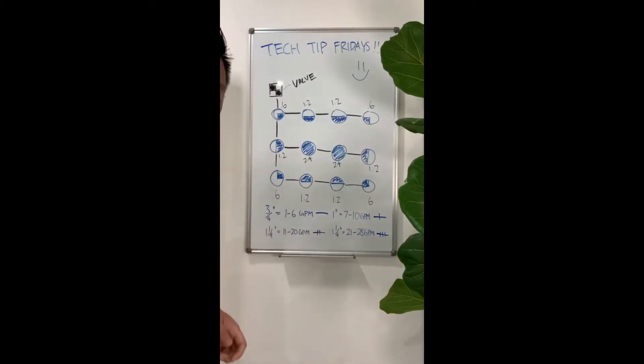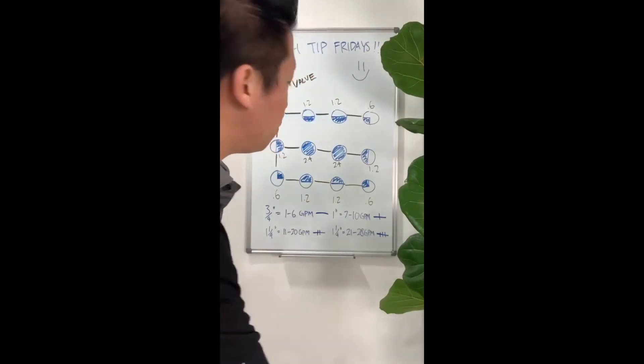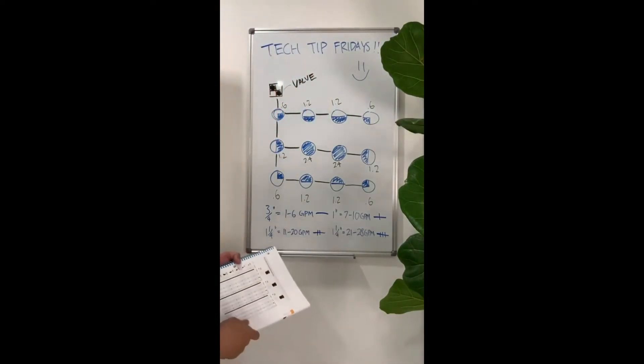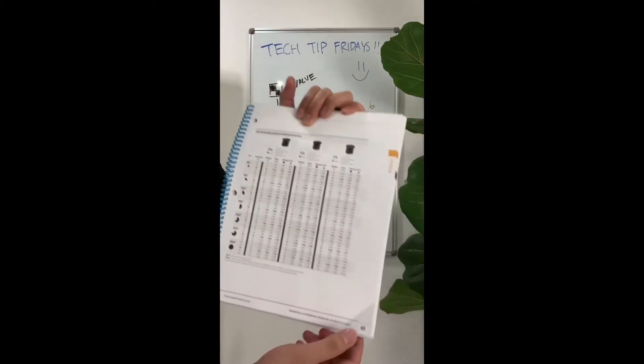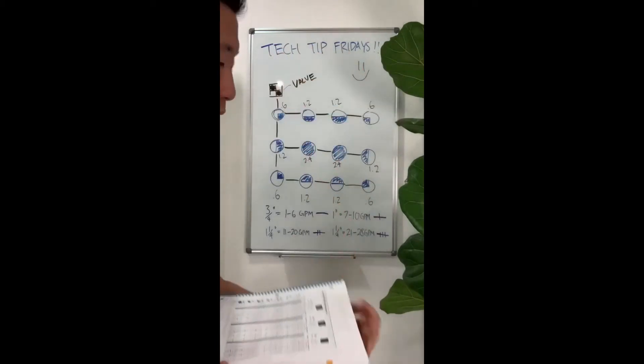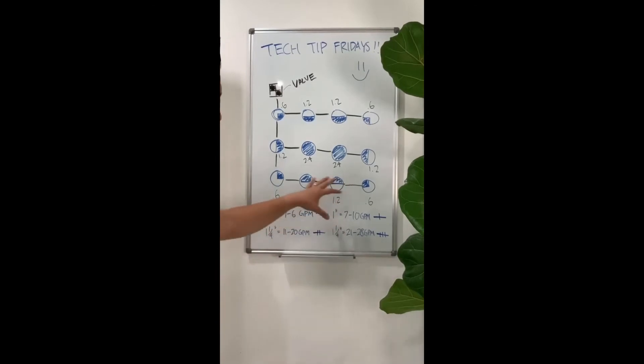Now, the other key piece of information that we're missing here that we'll need to do our pipe sizing properly is how much GPMs is each emitter emitting. So for today's example, we're going to be using the adjustable 12-foot nozzle on page 65. And I kind of marked it down here for easy reference as we're calculating for the pipe sizes.